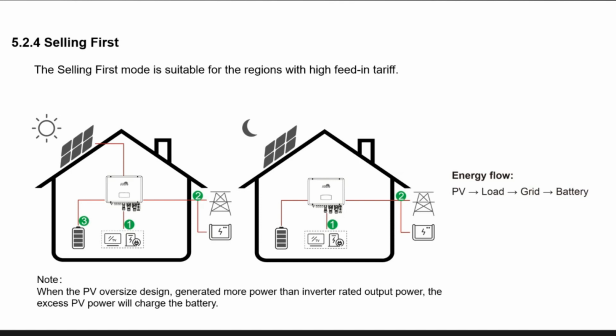Someone will have a question: because the grid is kind of a big battery bank, why does the inverter have extra energy for the battery? That is the reason when the PV is oversize designed and generates more power than the inverter rated output power, because the inverter's output power is limited. If the energy from the PV side is bigger than the output power of the inverter plus the local load consumption, the extra excess energy will charge the battery at the same time.